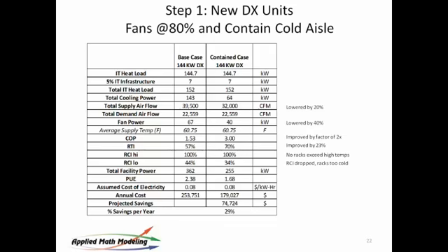But it opens the door to turning up, of course, the temperature. You can see the PUE went down here. Now we're at 1.68, and the estimated savings per year are 29%, about $74,000. At $74,000 a year, you can pay back a CRAC pretty quickly.